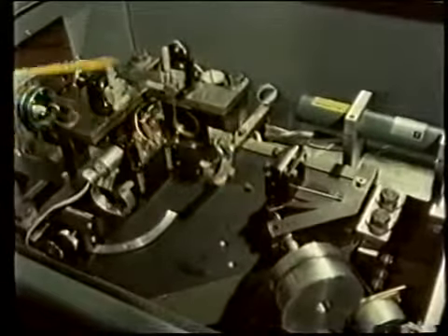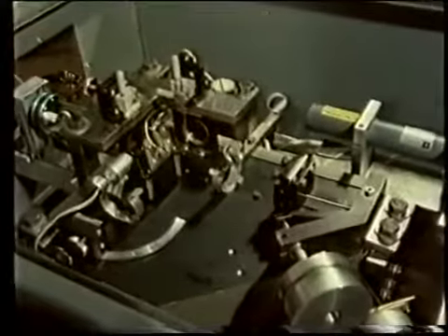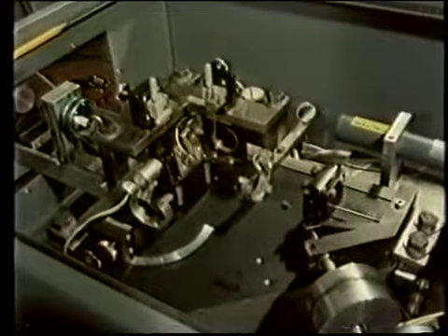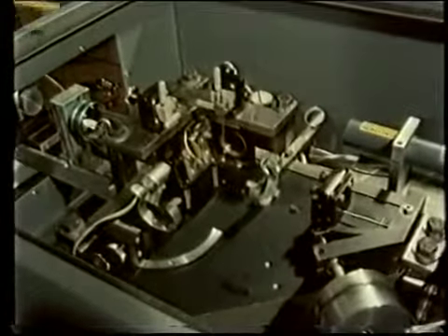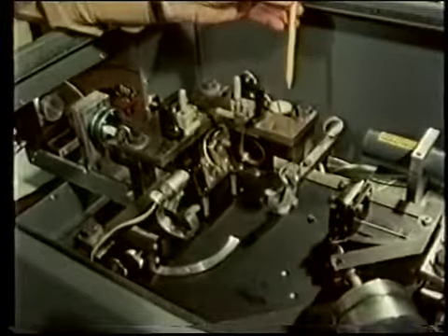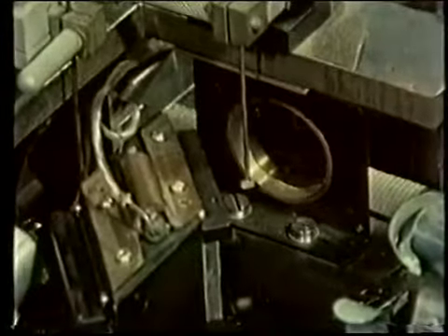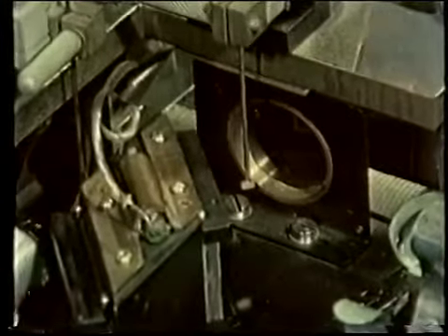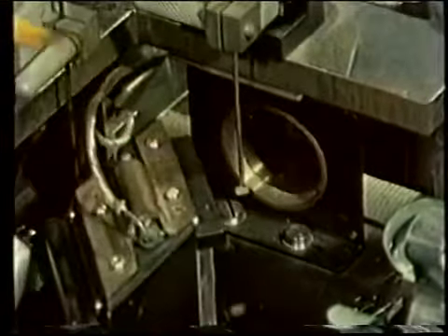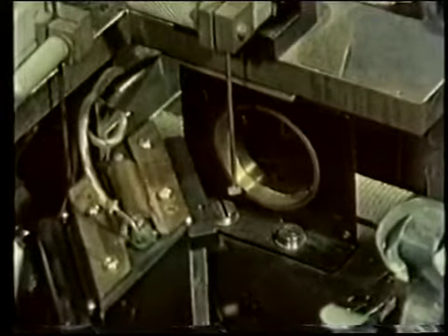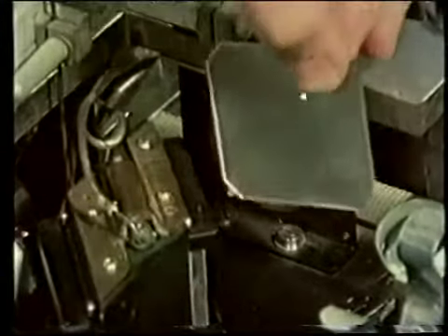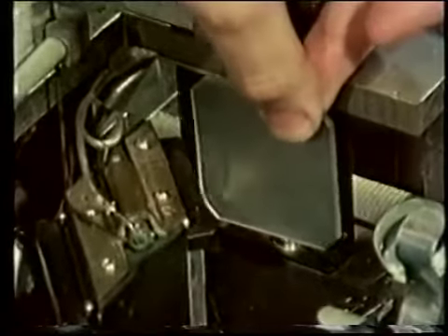There's also a laser and a couple of extra mirrors in this setup, but that's only there to enable the system to be calibrated. The source down here produces radiation, which is collimated into a parallel beam by means of this lens here. The lens is made of germanium and is quite opaque to visible light, and if I put in this piece of ground glass, we see absolutely nothing on it.